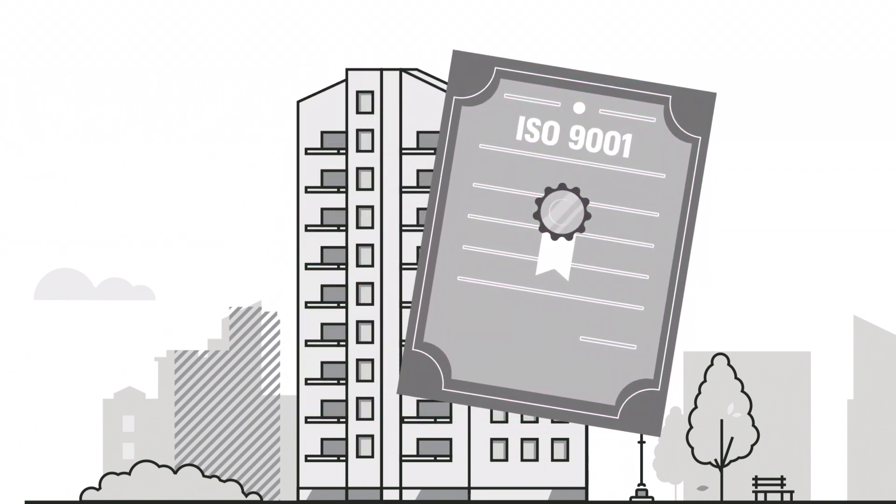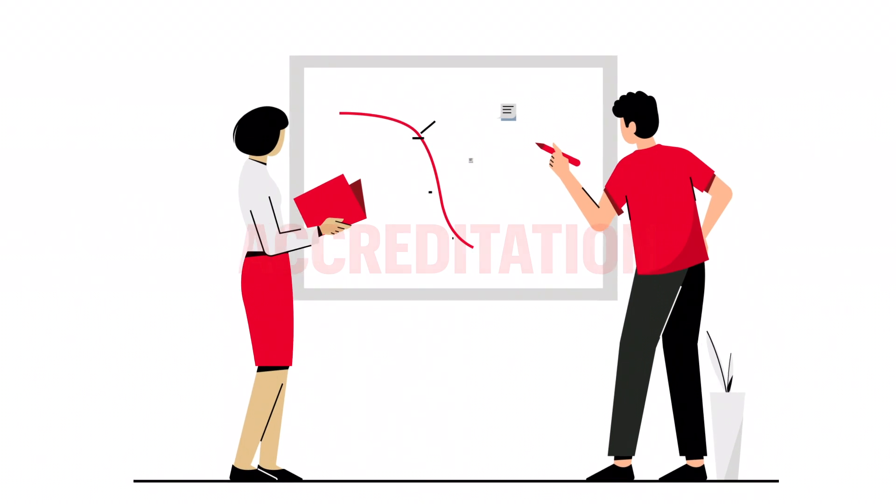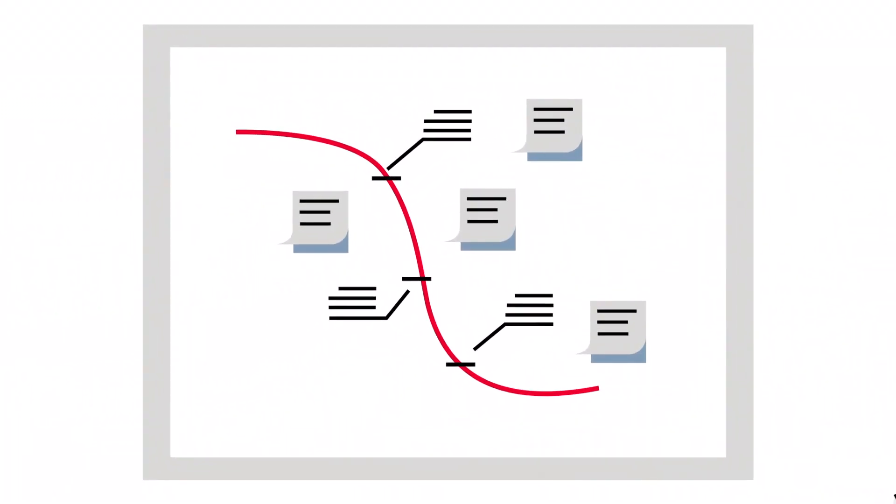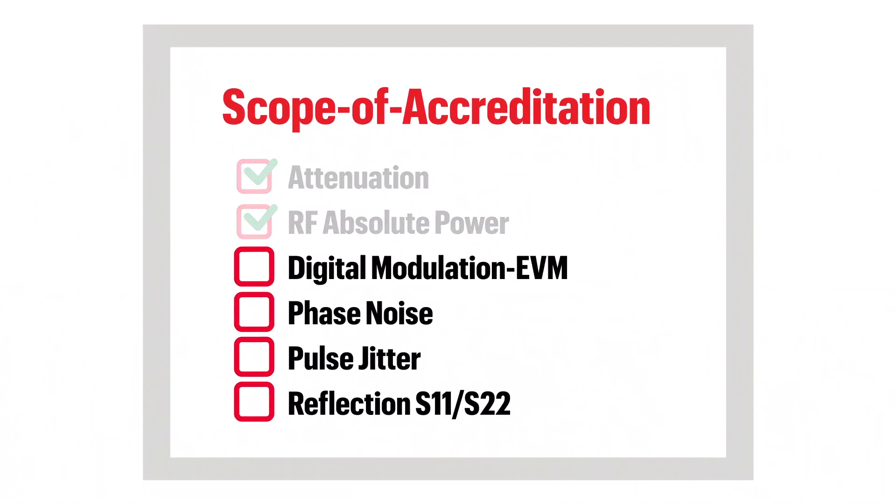Don't forget that claiming standards compliance isn't the same as actually complying. During accreditation, an impartial third-party expert assesses the lab's competence for specific measurement parameters. Sounds simple, right? Yet many labs actively offer calibrations involving parameters for which they were never assessed, immediately bringing into question the credibility of any results.